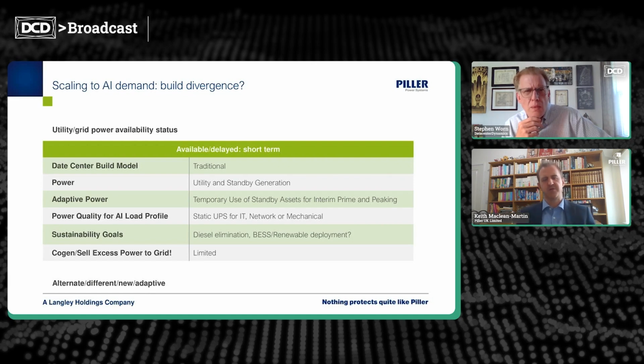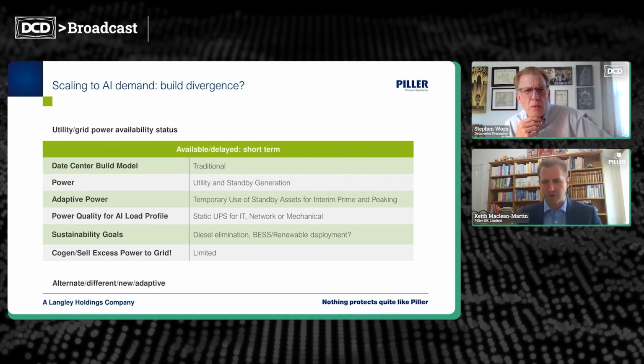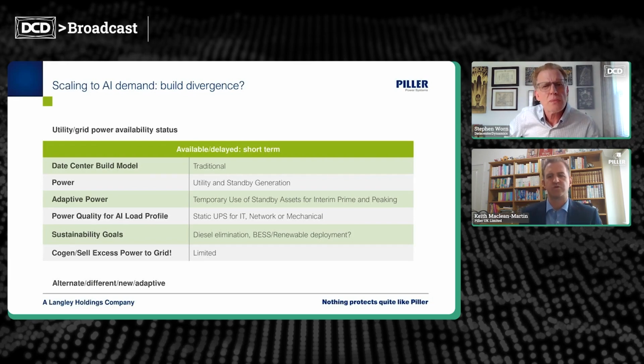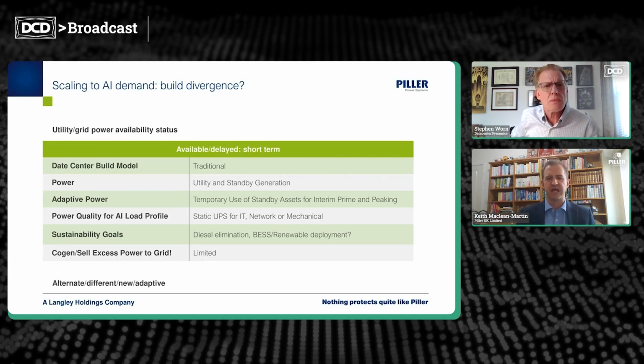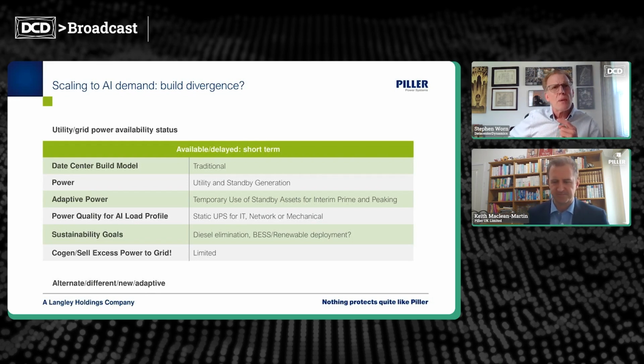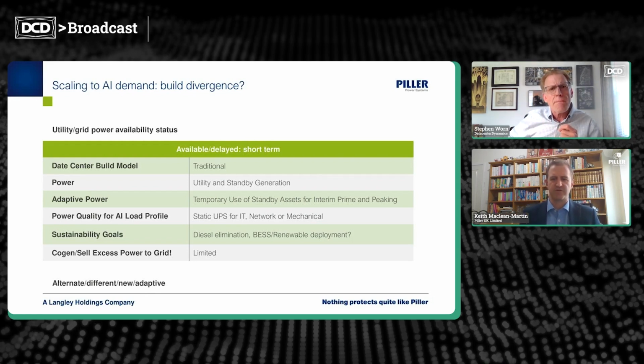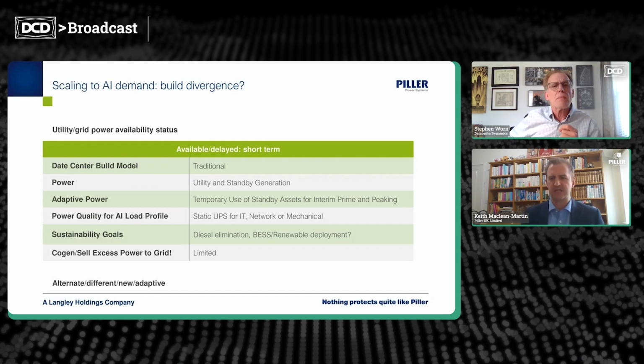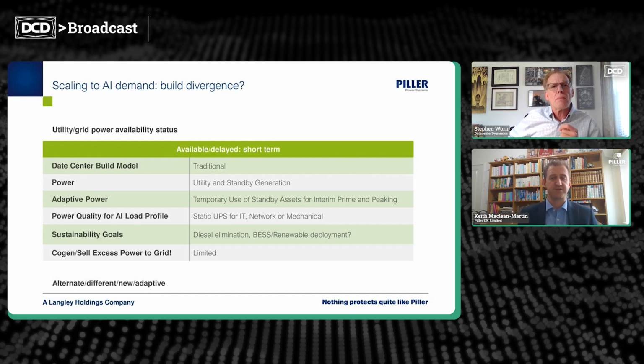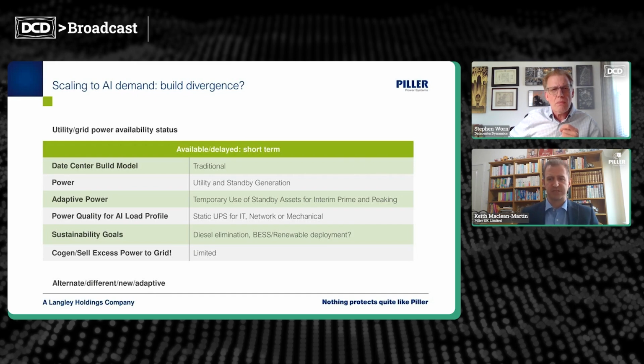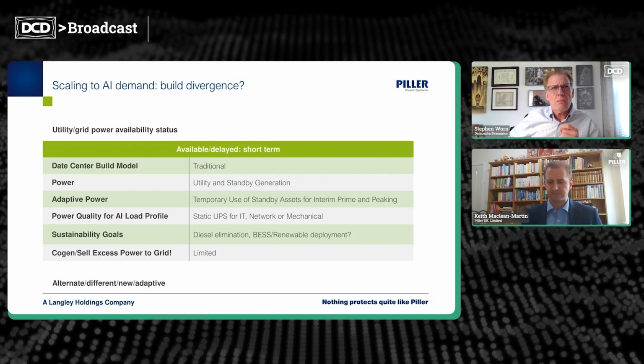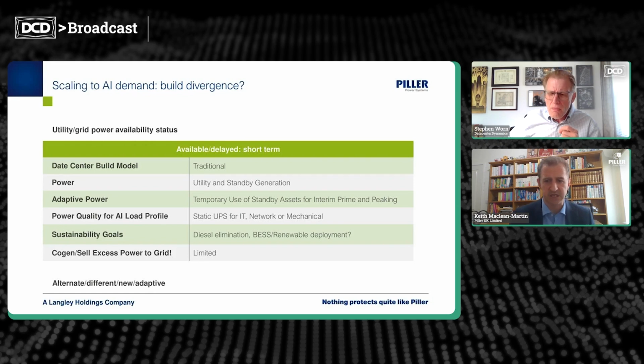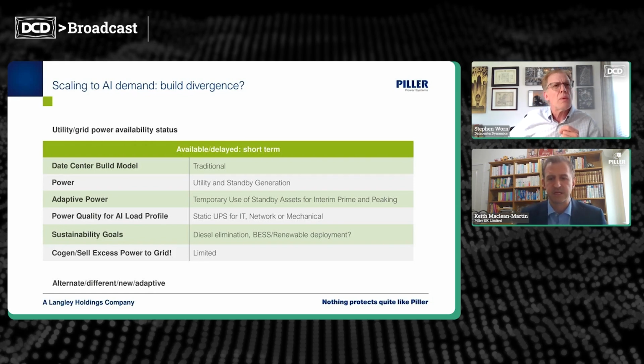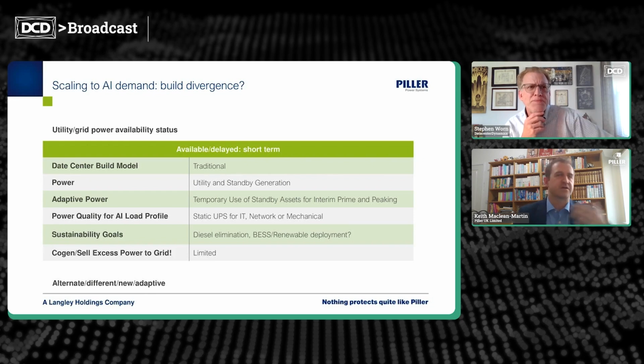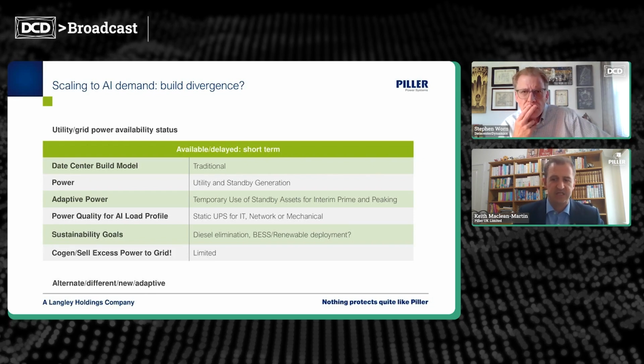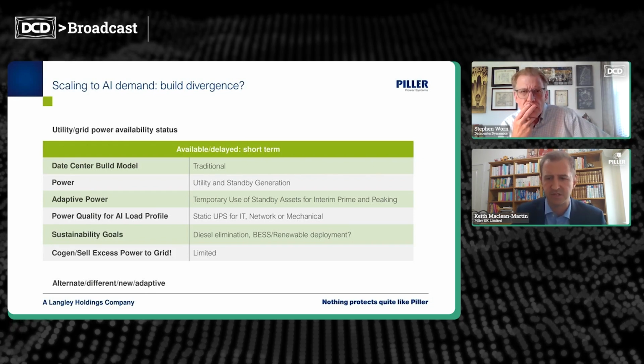But if we now have on-site prime power of a great quality, of availability, and the resilience that's known and from a guaranteed source, then the use of UPS in the traditional way is now obsolete. So infrastructure needs to evolve to power conditioning and stabilization technologies integrated as part of the on-site generation scheme. That helps to compensate the slow response of gas generation and alternative intermittencies introduced by renewable sources. The ability for perhaps cogeneration or grid services is a possibility and can help sustainability goals.